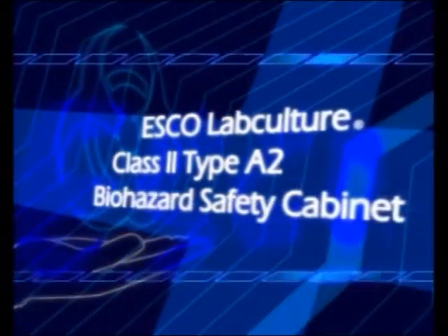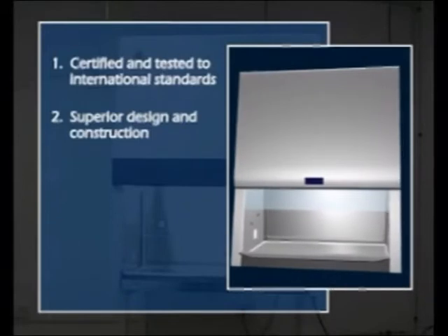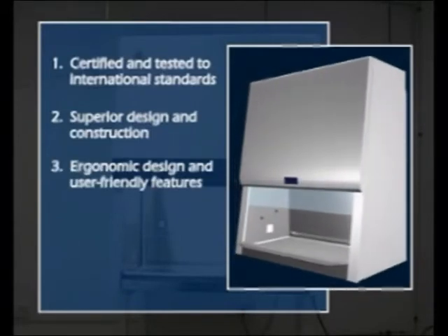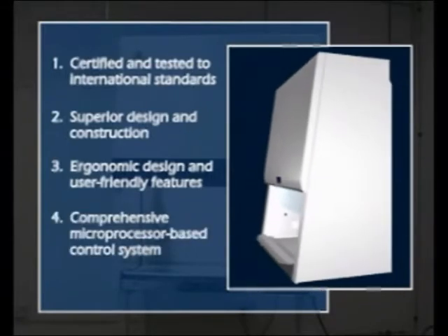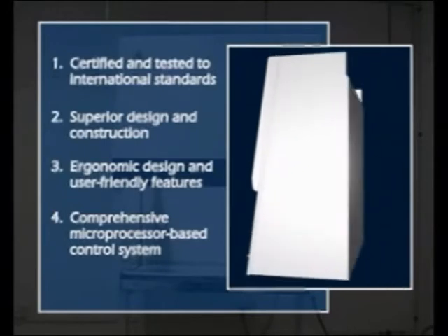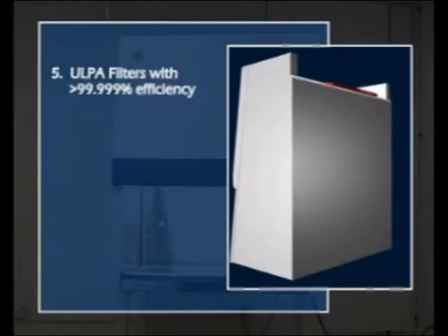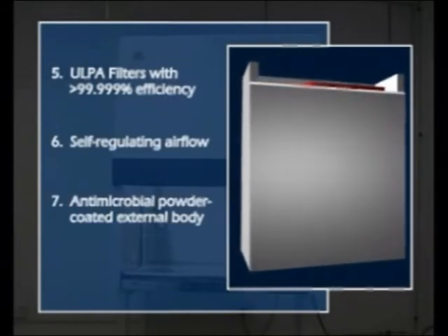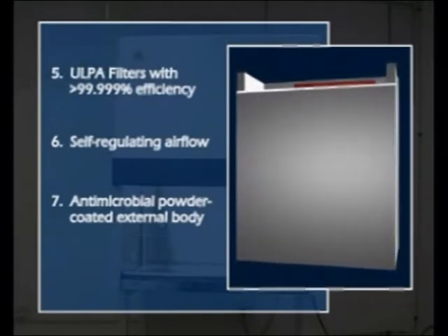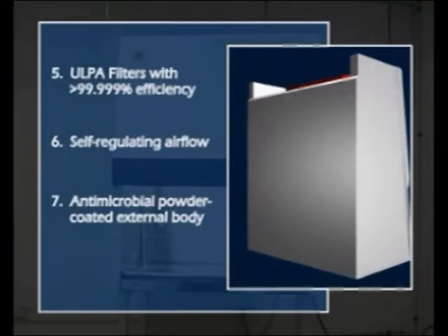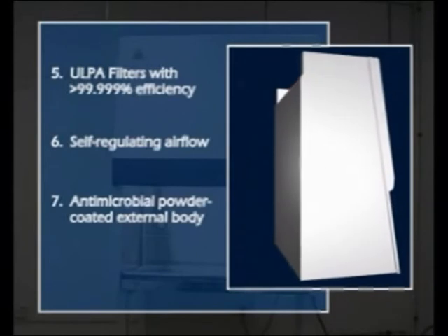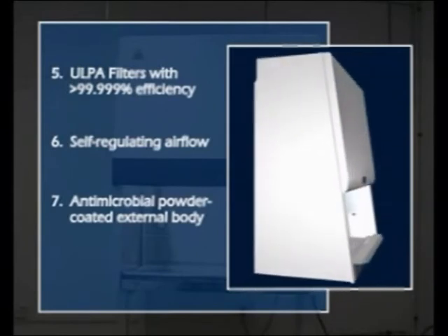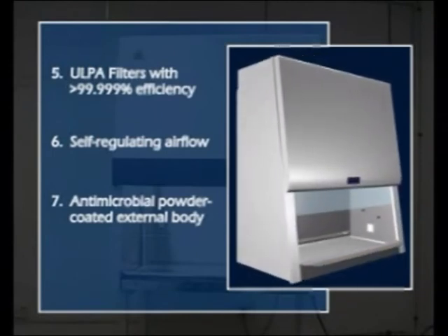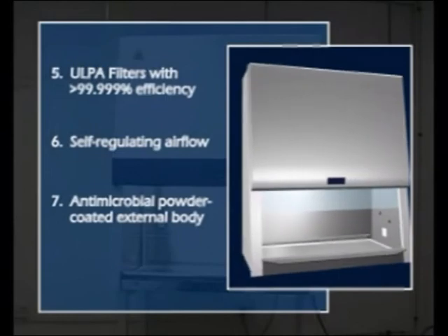The Lab Culture Class 2 Type A2 Biosafety Cabinet is certified and tested by independent test bodies to major international standards for Class 2 biosafety cabinets. The cabinet offers numerous user-friendly features such as a sloped front design and enhanced cleanability. The microprocessor-based control system provides the user with full monitoring and control of the cabinet performance. Superior design ULPA filters provide ISO Class 3 air cleanliness within the work zone, ensuring the best product and operator protection as well as environmental protection. The self-regulating cabinet airflow system ensures the best performance as the filters begin to load through normal usage. These and many other features make the Lab Culture Biosafety Cabinet an optimum solution for biosafety requirements of your processes and applications.